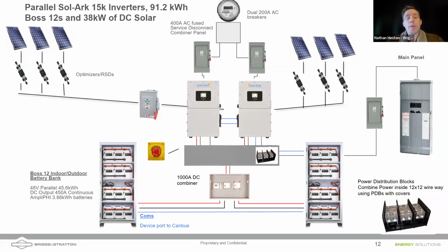And after the inverters, right, we would then parallel up the signal, the AC power coming out of those inverters, and then feed that into a single 400 amp panel if that's what the house has. We have the ability to bring in as many batteries as we want on almost any inverter. You're not limited to the batteries on your inverter, but you need to make sure the inverter has the ability to charge them, right? And here we're showing 90 kilowatt hours of backup that will run the average house for the better part of a week.